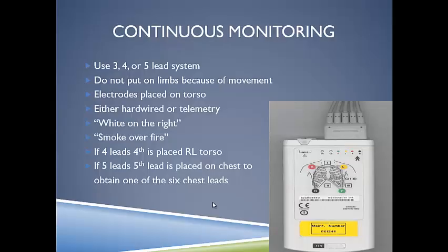It's either hardwired, meaning there's a cord attached to the electrodes which attaches directly to the monitor on the wall mounted at the side of the bed, or it's telemetry, which is like this little box here on the right-hand side where the electrodes lead to this little box which can be worn in a pocket or a pouch right on the patient and makes the patient more mobile.